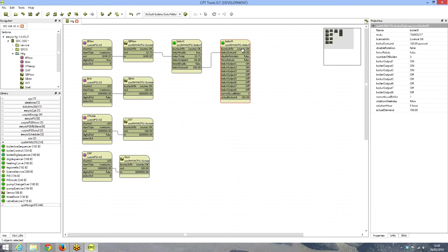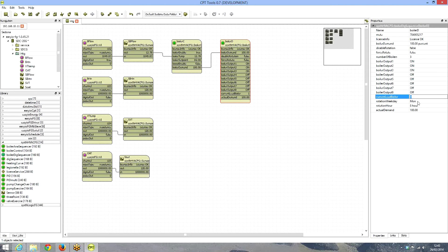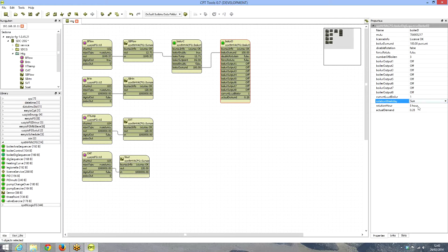Highlighting the digital boiler sequencer object, we can see the number of boilers is set to three — which is correct. Further down we can configure when to rotate: let's set it to Sunday at 8 o'clock in the morning. The next thing is to link the sequencer outputs to the digital outputs.